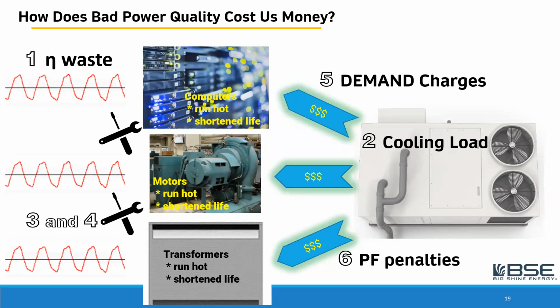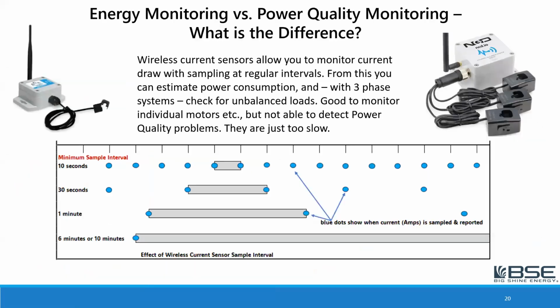As we saw, if everything's running a little hotter than it should, it means we're drawing more power than we should. So month after month, we'll pay a little bit more for those demand charges, so many dollars per kilowatt of demand. And also, we may pay more money for power factor penalties. So very often, utilities will require a penalty, a fee, if our power factor drops below, for example, 0.9. So all of these things are affected by power quality and efficiency, and therefore we want to optimize our operations.